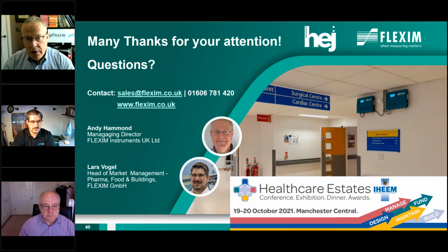Installation, if we're looking at portable meters and clients purchasing their own portable meters for their own surveys, if it's liquids, anyone can do it, I would say. But if it's gases, we would provide training alongside the instrument to train you how to get a gas measurement or a steam measurement. But if it's a fixed installation, then obviously we would provide commissioning services, or indeed we sometimes supply through medical gas pipeline installers, and those companies that we deal with have been trained as well to do commissioning. Thank you.